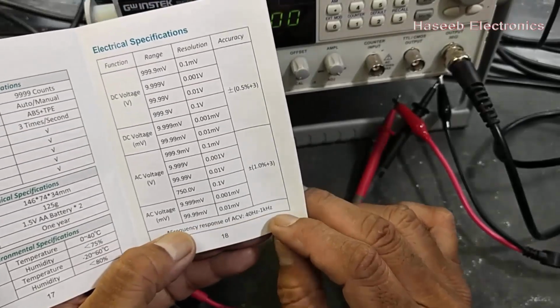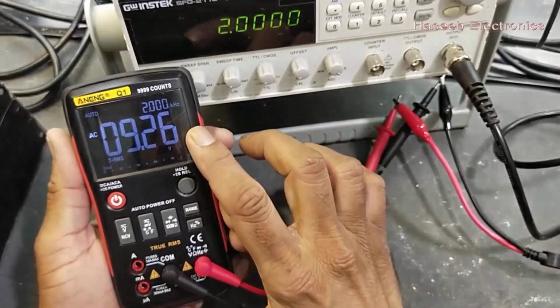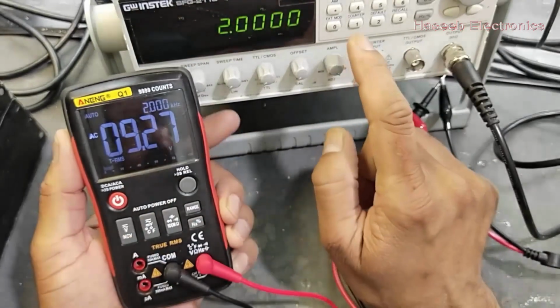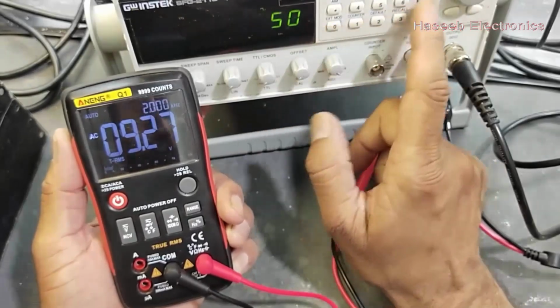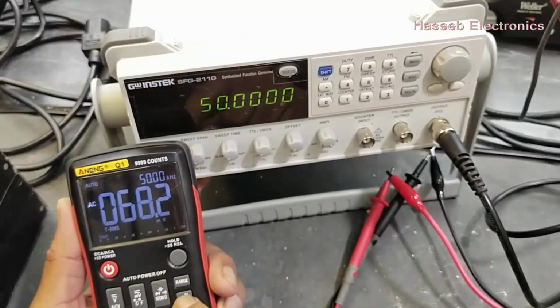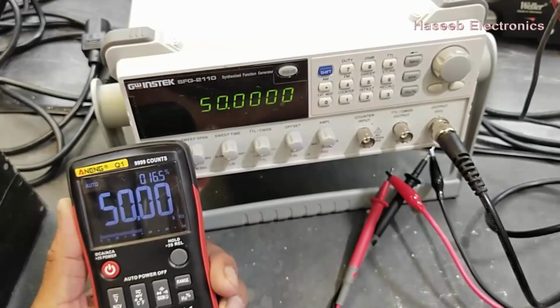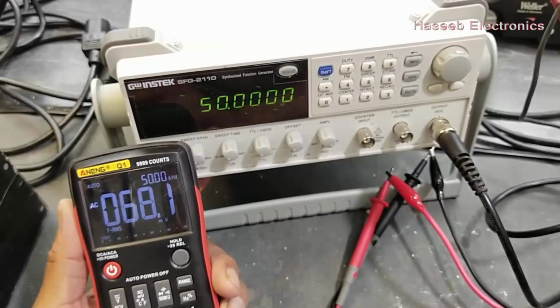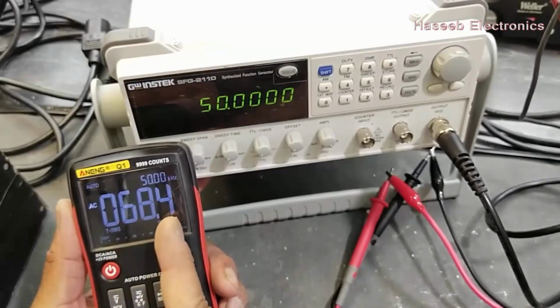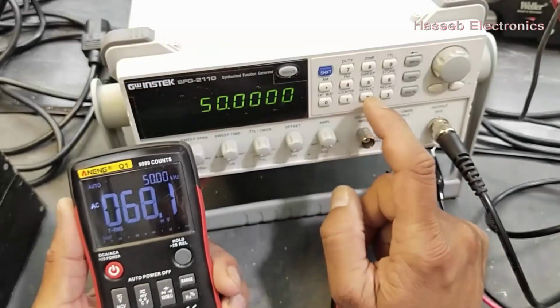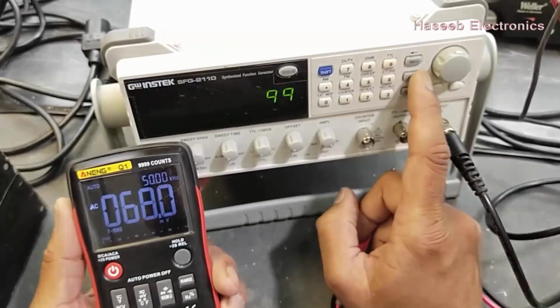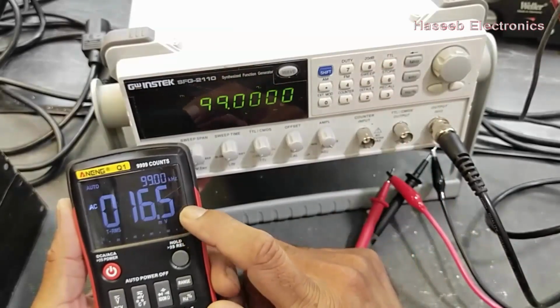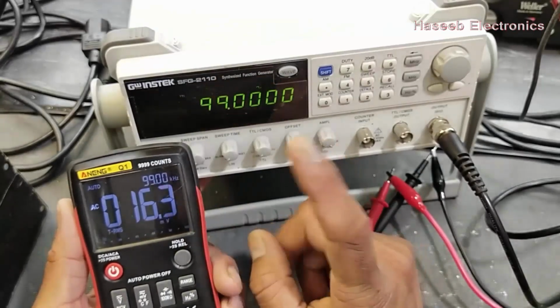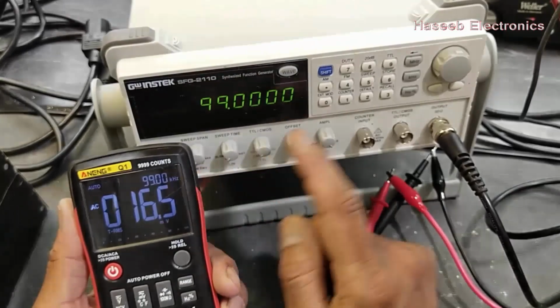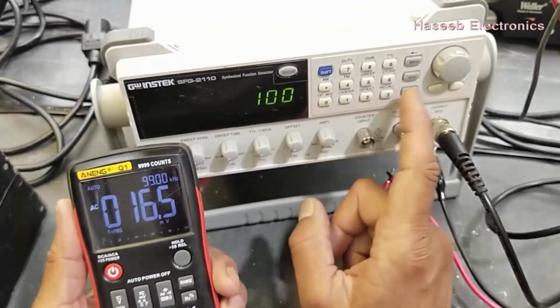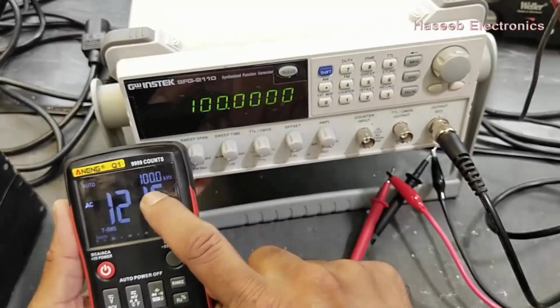We have to check the operator manual. We can measure up to 100 kHz frequency here in the same AC voltage range. I will set 50 kHz. It is giving 50 kHz. Check frequency here, 50 kHz. But if we check voltage, the voltage dropped to 68 millivolts. If I set 99 kHz, the voltage dropped to 16.5. We can check frequency here up to 100 kHz. So that is 100 kHz frequency here.